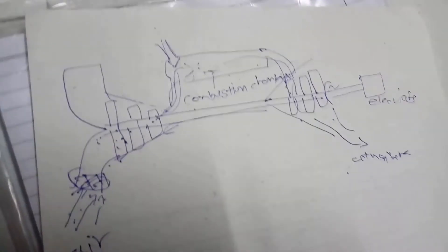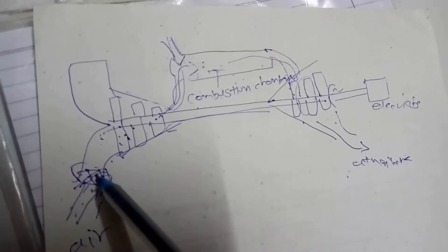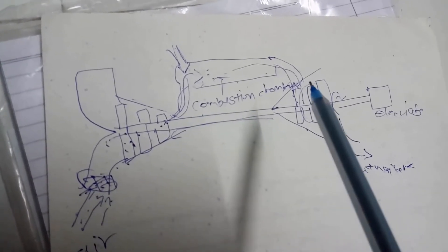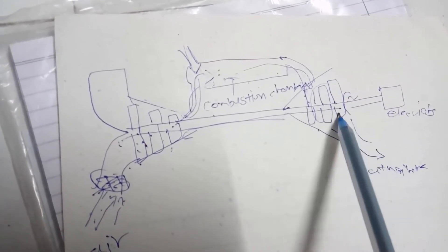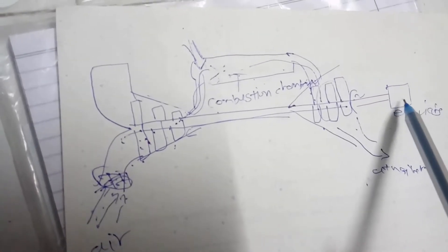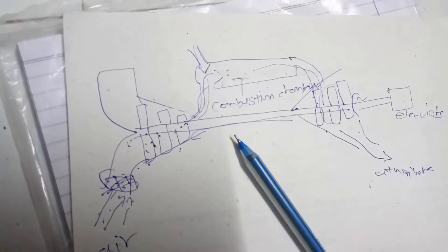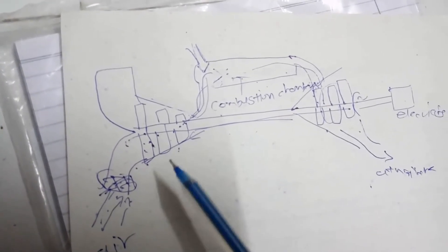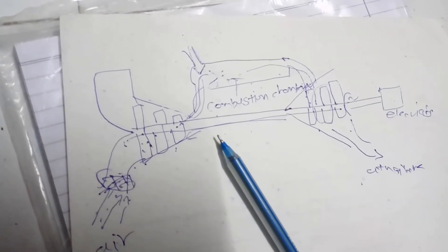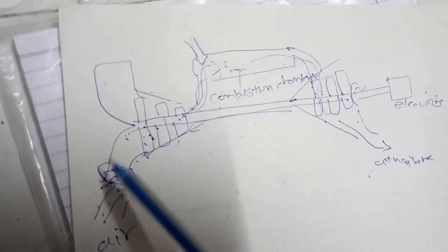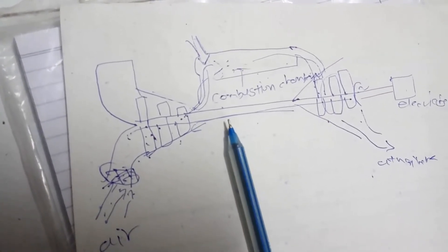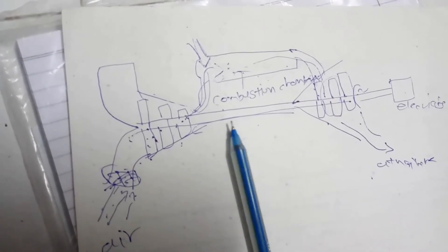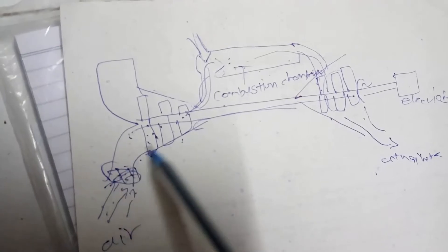The main advantage of the open cycle gas turbine power plant is its very simple design. There are few rotating parts — the shaft and blades — and these rotating parts produce electricity. So the problem of vibration and lubrication is not that much. Another advantage is that the weight of this gas turbine power plant is very less compared to the power it generates. And it does not require any cooling water.